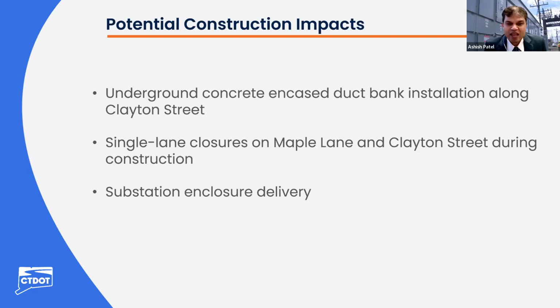The proper maintenance and protection of traffic signage will be provided prior to construction start of this underground concrete encased duct bank. The vehicular traffic will be guided by traffic police. The temporary H20 rated steel plate will be used to cover the open portion of the underground concrete encased duct bank during the concrete curing process. It will allow vehicular traffic flow during the night time. The existing sewer, water, and electricity on Clayton Street and Maple Lane will not be affected by this project.